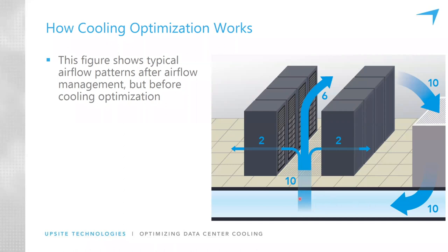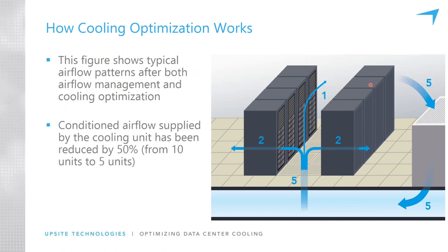We're now delivering all that conditioned air out of supply tiles in a cold aisle, but the IT equipment still only needs a total of 4 units. So now there are 6 units of bypass airflow leaving the cold aisle. But this is still a good thing. We're stepping in the right direction, because now we've created an environment where we can make adjustments to the set points and reduce the amount of air moving through the cooling units. Now take it down to 5 units of air, so that we're delivering 5 units of air into the cold aisle. The IT equipment needs a total of 4, and we've got 1 extra unit of conditioned air. Always good to have a little extra for variations in flow rates through IT equipment and a slight positive pressure. And now we've reduced the flow rate through the cooling units by half. And that has a dramatic effect on the energy consumed by those cooling units.